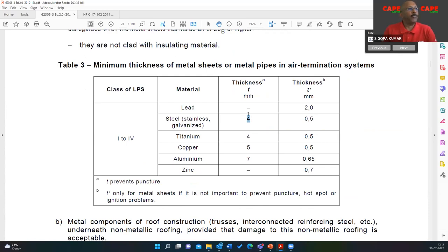Number two, if the thickness is between 4 and 0.5, actually in India, we don't use 0.5. I think our sheet is even thinner than this. If the thickness is between these two, 0.5 to 4 millimeters, lightning may create a puncture on the sheet, and that puncture probably can ignite some other fire or some other accidents. If you want to avoid puncture, in this case, between 4 and 0.5, you have to use an air termination system. That means you make a mesh and connect the mesh to the sheet itself. You avoid direct lightning hit onto the sheet. Very simple. And if the thickness of the sheet is less than 0.5 millimeter, it is dangerous to use the sheet as air terminal. You must use a properly designed air termination system on the roof.